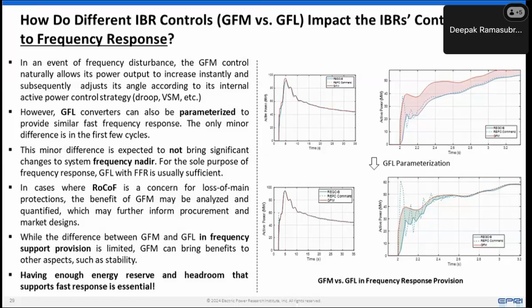Because there is a question that keeps coming up: is this frequency decline that we are seeing because of the type of inverter? And is there something that we can do based on that? What we really identified is that it's the first few cycles that matter, that have a change in the response. You can have a non-grid forming device parameterized in a way to provide fast frequency response at the inverter level.